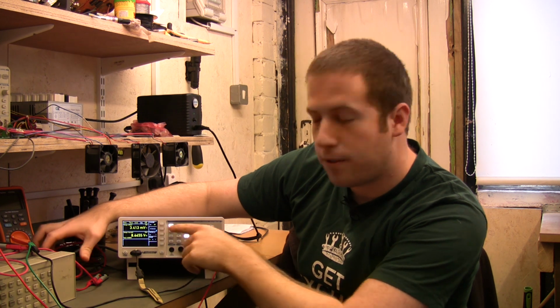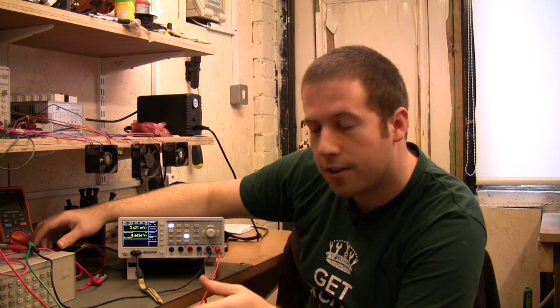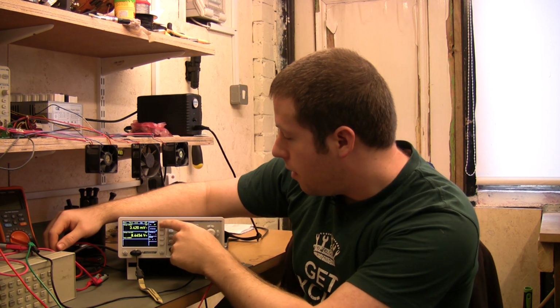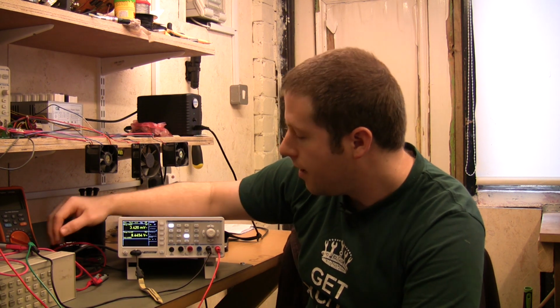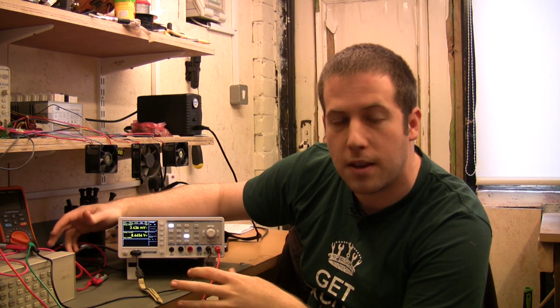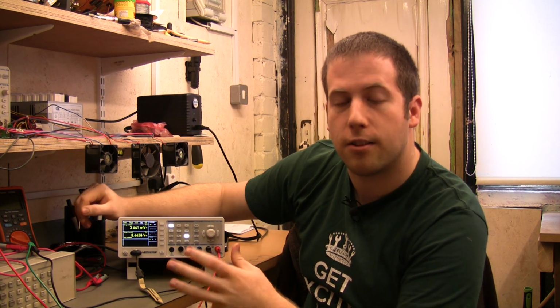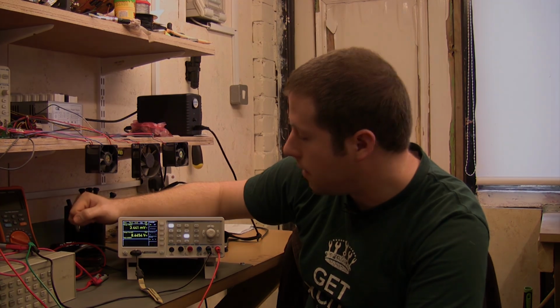You can also set an interval on here. We've got it set up for 0 seconds. That's just going to log as fast as the ADC can read. So let's turn logging on. We're now logging into our USB stick. Also, we've tried this out with lots of different USB sticks. As I mentioned, we're using a 16 gig USB stick at the moment. So far we haven't had any size USB stick that's failed to work at all. So yeah, it seems to work nicely.